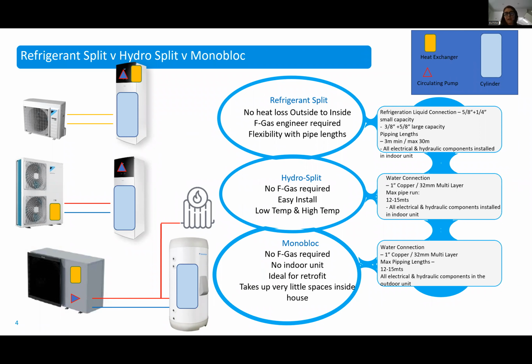Most people would be familiar with refrigerant splits and monoblocks. The hydro split is an in-between product, which allows you to have the nice integrated indoor unit, but to have a water connection between the indoor and the outdoor. So it fits into a nice, easy to use, easy to install category, generally used in larger one-off properties. Also, that would be a medium temperature heat pump, so it goes up to 60 degrees in domestic heating. They're a very good option for retrofit solutions. So I hope that gives you the difference between the three types of systems, because if you're not used to the technology, I suppose it can be a bit confusing.